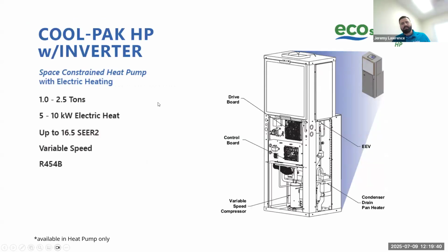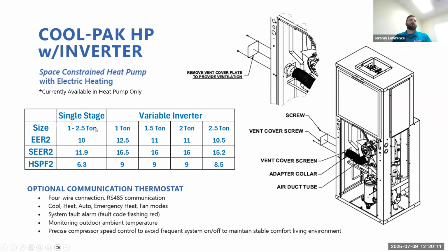The new addition. So, like I said, for the last 30 years, we've been working with these units with a single stage compressor. Very simple on-off basic controls. They have now just this month launched this new inverter drive system. It gives us much lower heat pump operation down to 0 degrees Fahrenheit, variable speed, and up to 16.5 SEER2 operation. From our old units, all sizes between 1 and 2.5 tons, our EER was 10, SEER was 11.9, and HSPF2 of 6.3, and just tremendous increases using a variable speed inverter compressor. They are rotary compressors. So pushing up into 12.5 EER, 16.5 SEER, and 9 HSPF2, which I believe meets rebates for the US market.